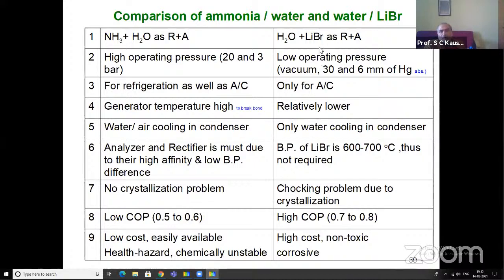But in case of water lithium bromide, because lithium bromide is a solid, at lower pressure and lower temperature, there is a problem of crystallization. So there is a problem of choking of the system operation due to the crystallization of the lithium bromide during system operation. Now, because the water vapors are associated with the ammonia vapors, the cooling capacity is lower. So COP is also lower.